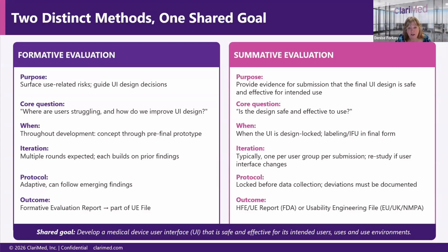So, depending on your organization, the size, the culture, everything else that can tailor that, you can decide how you want to handle it. But at a minimum, you have to discuss your formative evaluation plan as part of a user interface evaluation plan. So some clients, we guide them to do an overarching plan, and then as it makes sense, have individual protocols for the formatives just to help guide your team on what exactly your goals are and how you're going to accomplish that goal.